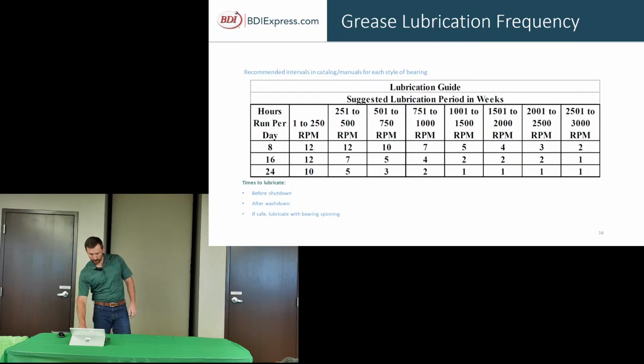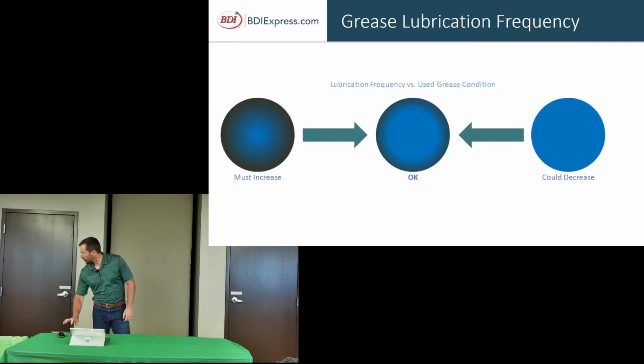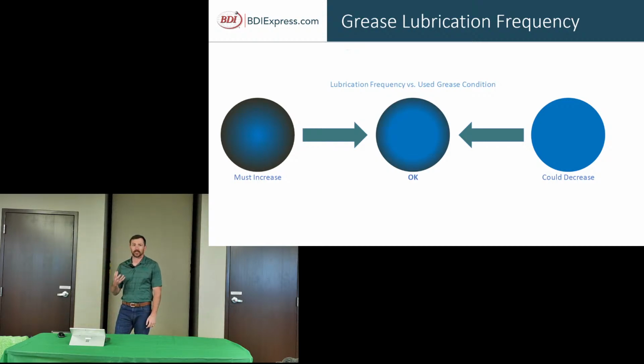And then this is that little chart. So if your grease looks like it's coming out of your tube, that's you're purging out. You probably have too much grease in there. Right on your guys' left, where it looks kind of burned up, that means you need to increase your grease. And then right in the middle, where it might have a little bit of that burnt up, broken down grease, and the color of your grease that's coming out of your grease tube, you have a sufficient amount of grease.